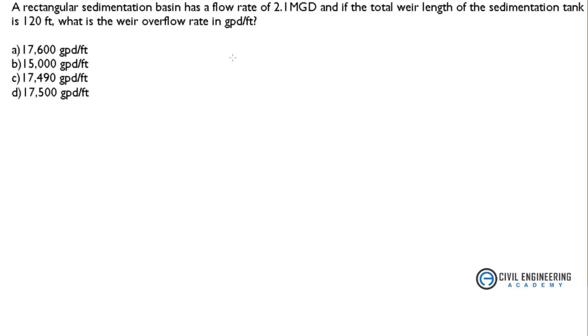A rectangular sedimentation basin has a flow rate of 2.1 million gallons per day and if the total weir length of the sedimentation tank is 120 feet, what is the weir overflow rate in gallons per day per feet? So we have to calculate weir overflow rate.